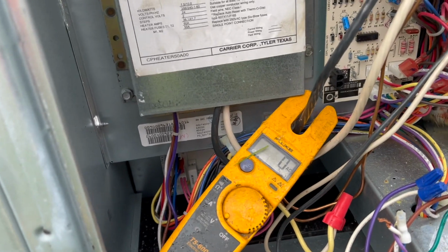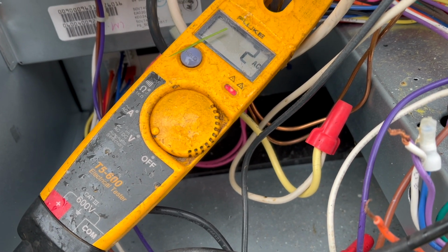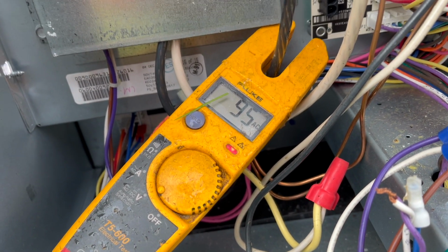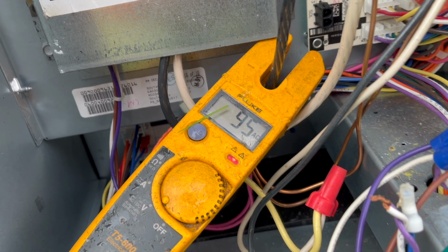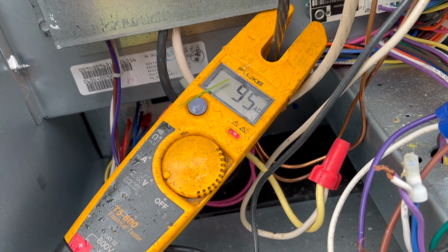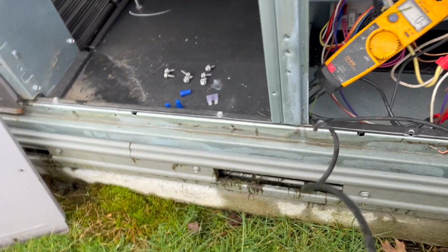Well, I've got both of the plugs off the motor undone, and if I check the transformer, I got 27 volts. If I check from the brown down here to the common, I've got 95 volts. That's crazy. I gotta see what's going on with this brown wire.